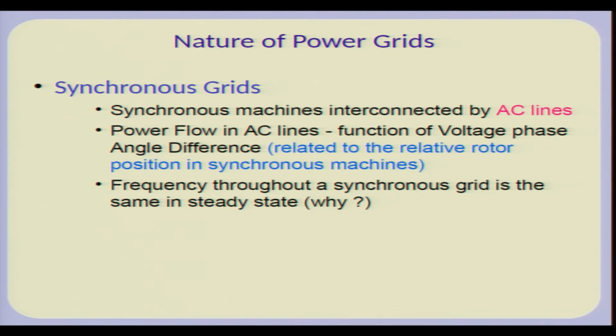Now, one fact we have learnt before is that in steady state, the power flow in AC lines is a function of the phase angle difference between the voltage at both ends. For a lossless line with series reactance X, the power flow is V1 V2 sine(delta1 minus delta2) by X. So the power flow in a transmission line is also related to the relative rotor position in the synchronous machine. There is a relationship between a mechanical variable, the relative rotor position in synchronous machines, and the voltage phase angular difference which appears across transmission lines. This we will illustrate with a simple example.